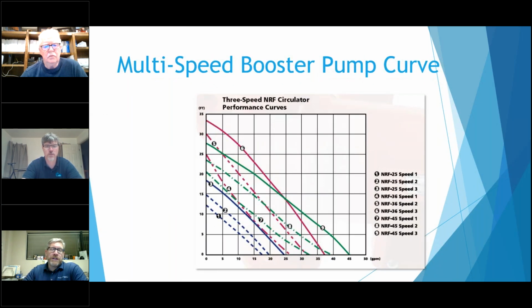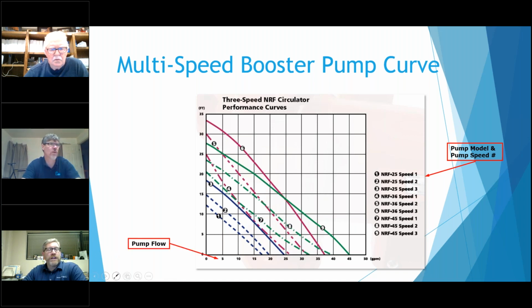You got multi-speed curves here. So it's very similar, basically you got a model and speed on it. We've got 3 different models, the NRF 25, the 36, and the 45. You got 3 different speeds that you can dial in for these pumps. And you still have the pump flow and head shown on the bottom and the side.